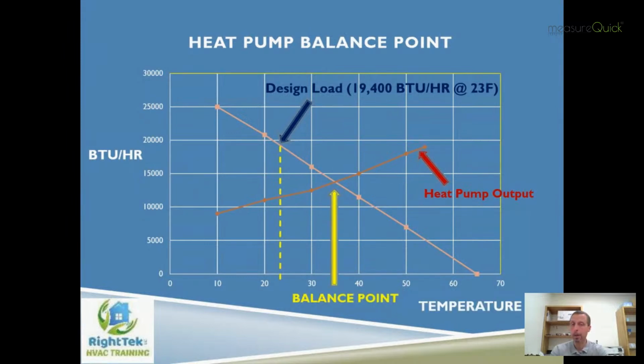That is the temperature where, if I did a good load calc and did all my design work and preparation correctly, I can figure out where that system should be able to carry that house down to, at least on the theory side of this. So roughly about 35 degrees is what I'm looking at here. Well, that does two things for me.